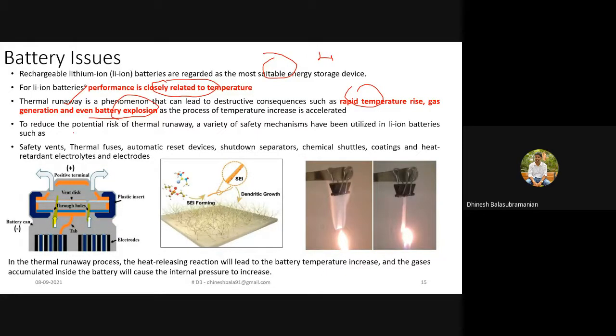To reduce the potential risk of thermal runaway, a number of safety devices have been incorporated into the battery. One such safety device is the safety vent. Because of the electrochemical reaction, there is a huge possibility of gas formation. Once the battery is completely enclosed, this would create excess pressure inside, and the entire battery might even burst. That is why the battery has a small vent or through-hole in the head of the battery, to release the excess gas created by this electrochemical reaction.